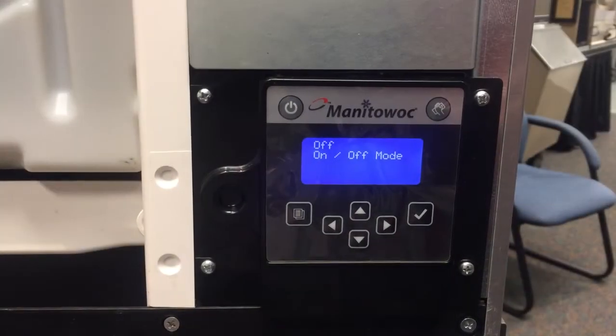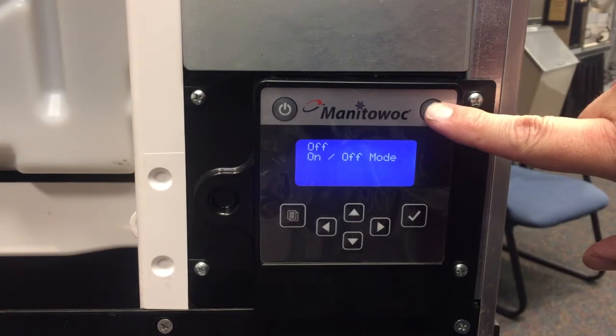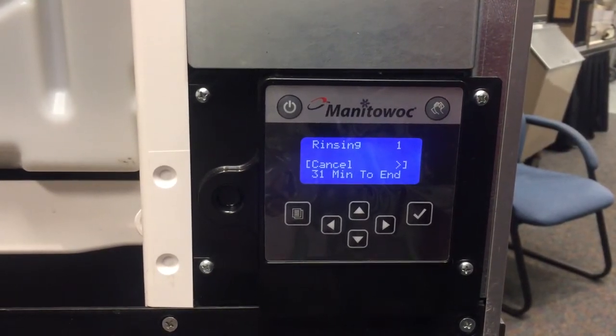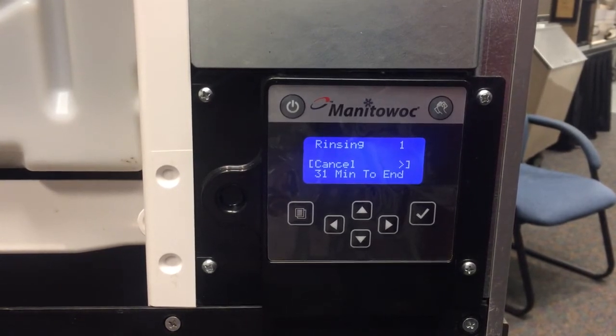The last few steps are to put the panels back on the machine, plug your machine back into the outlet, and then press the clean cycle. This will purge the chemical into the tube and prime it for the next cycle. Let it run through its 30-minute clean cycle, then return it back to ice making, and you're ready to go as far as the setup of that AuCS system.